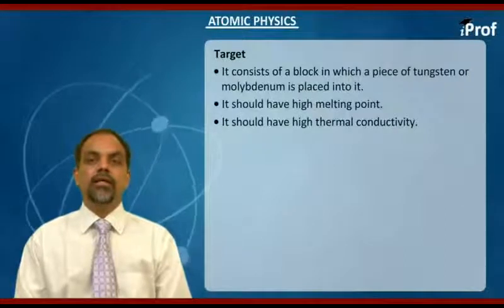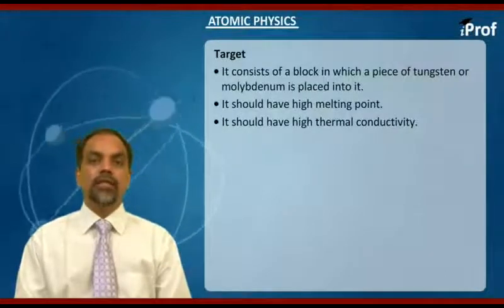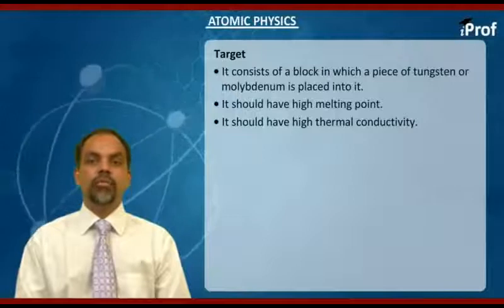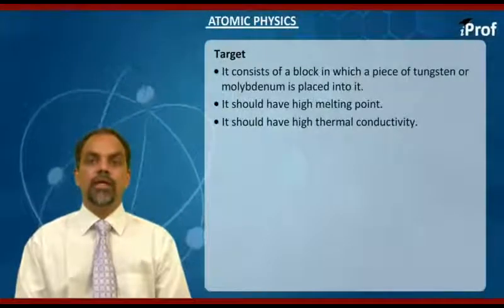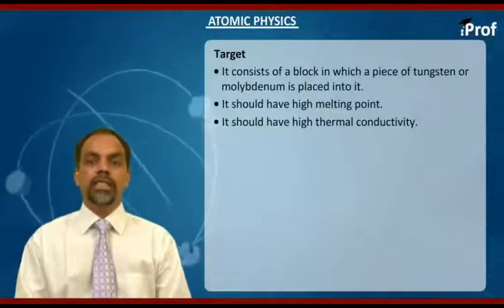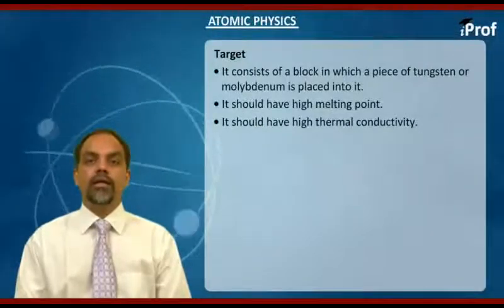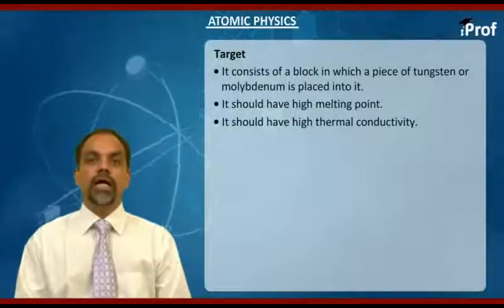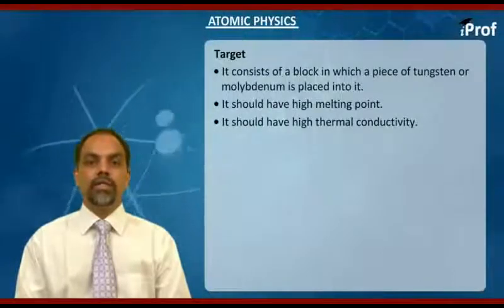The second desirable property or characteristic of a target is that it should have high thermal conductivity. Again, as I said, enormous heat is generated in X-ray production, so we would like this heat to be carried out of the system as early as possible without damaging the equipment. So it is desirable that the target should have high thermal conductivity.